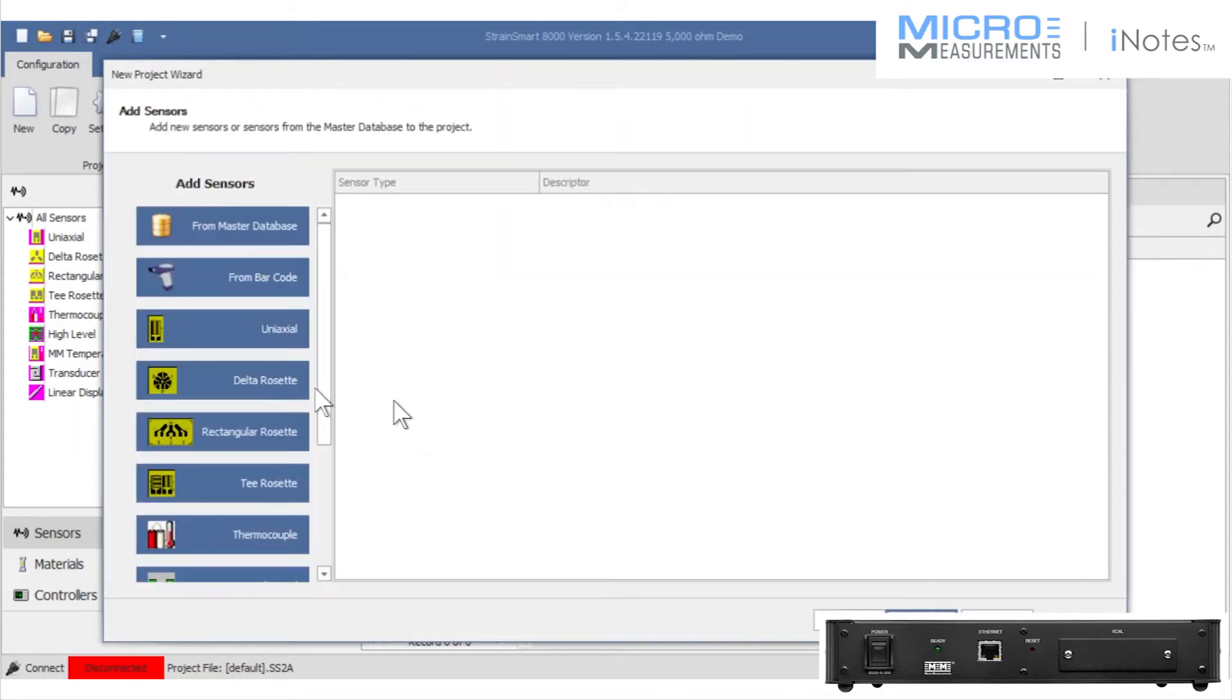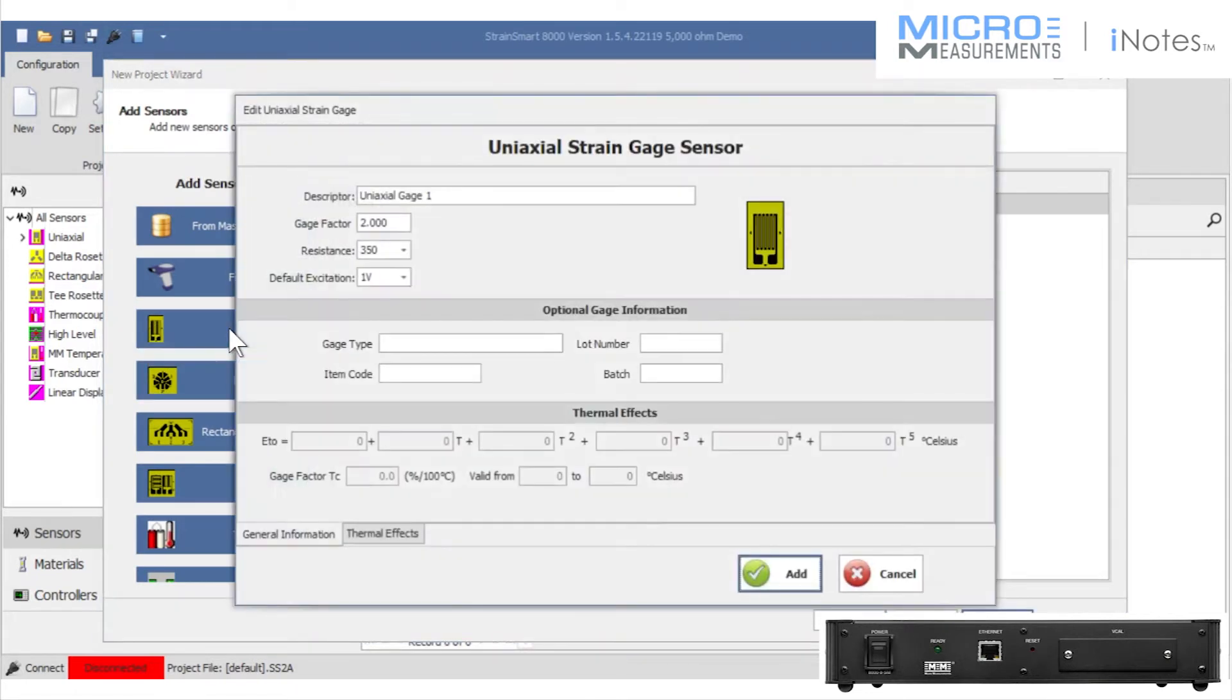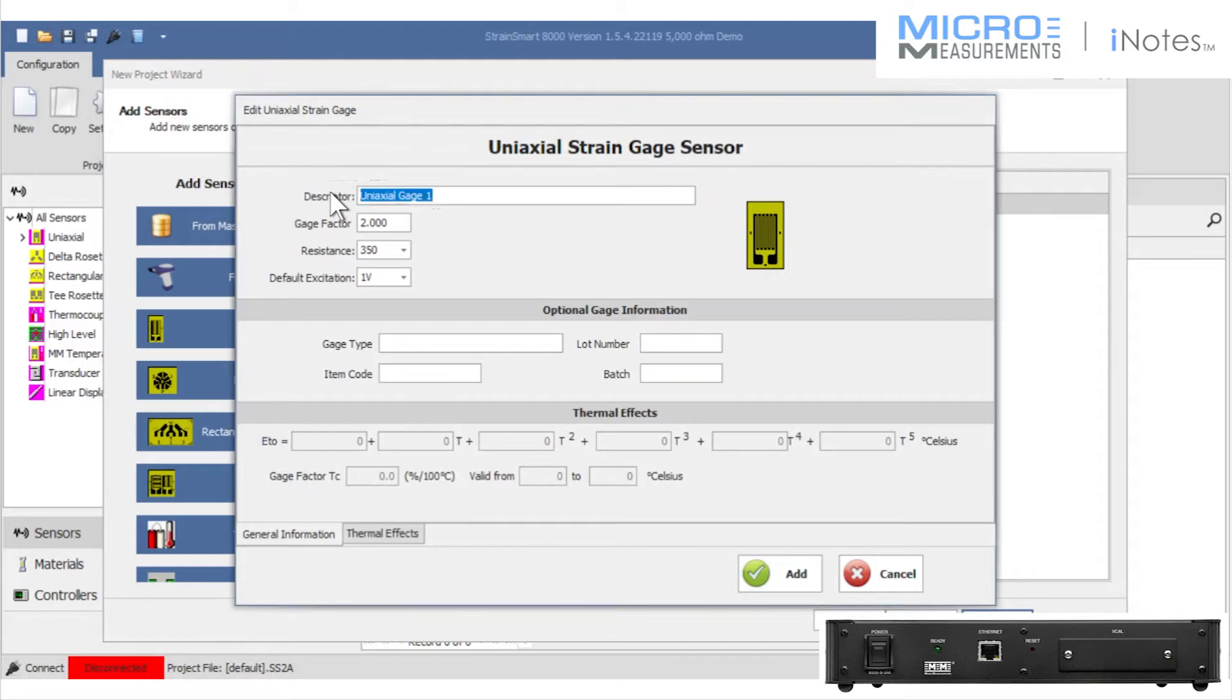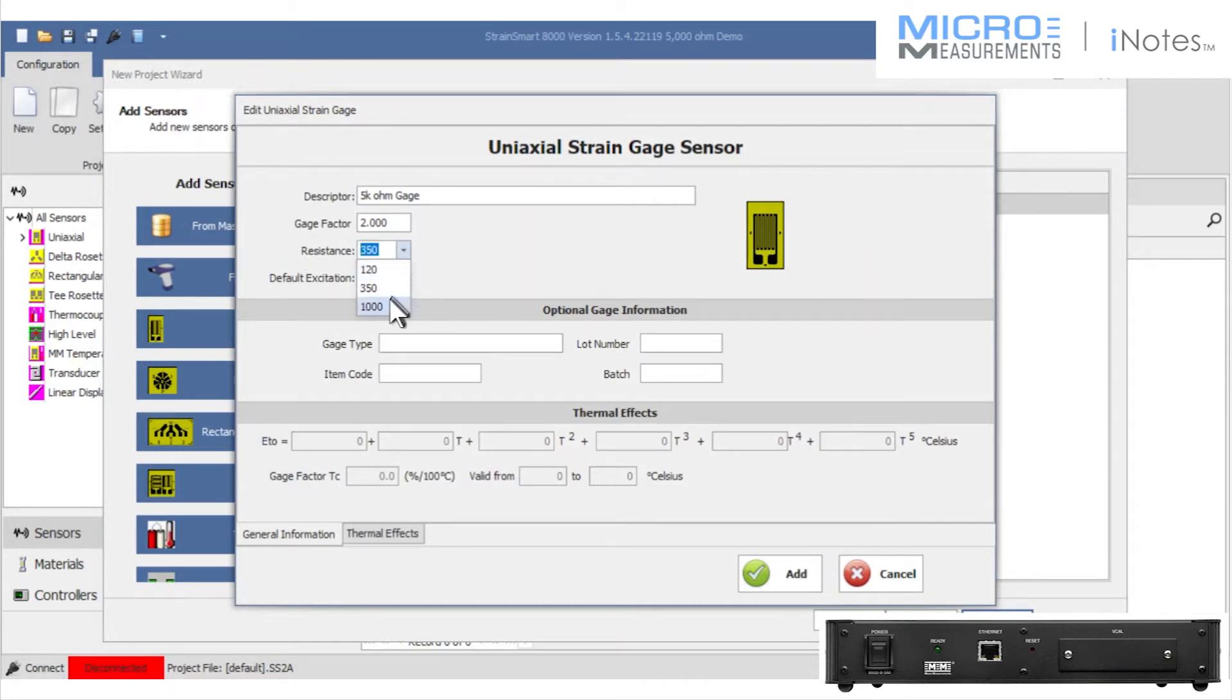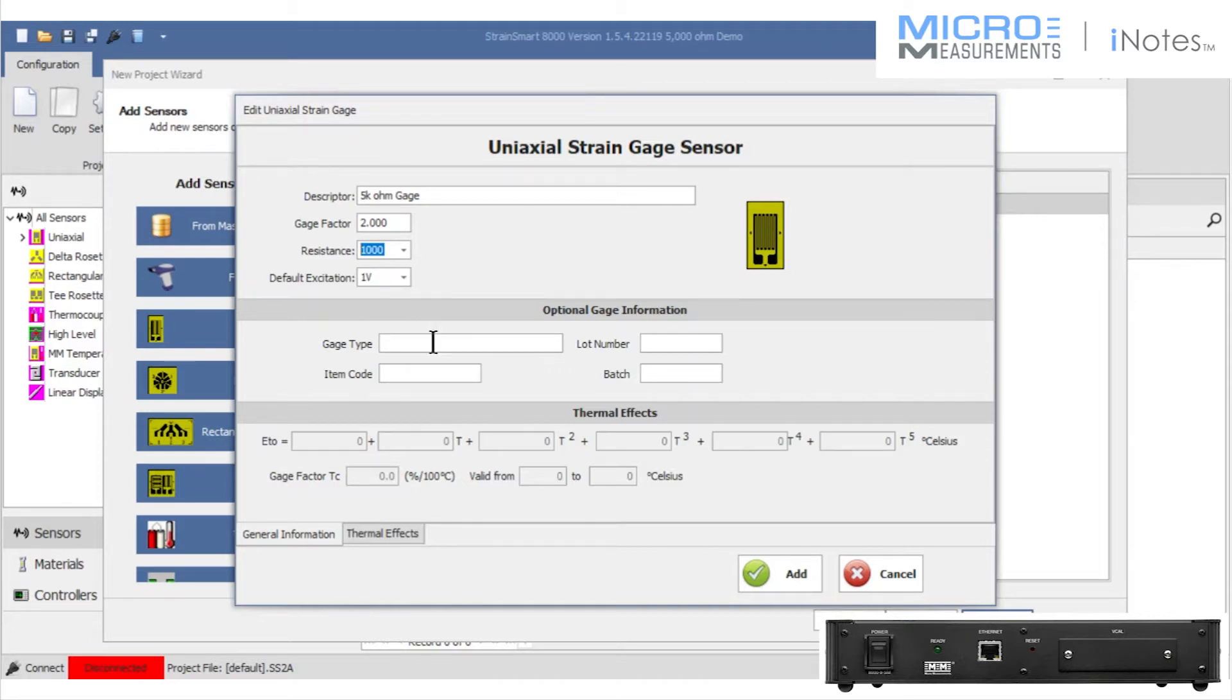StrainSmart allows me to declare the types of sensors that I'm inputting. I'm going to call one of them the 5,000 ohm strain gauge. I'm going to utilize the slot for what's supposed to be a 1,000 ohm quarter bridge. We know that I've changed it out to be 5,000 ohms.